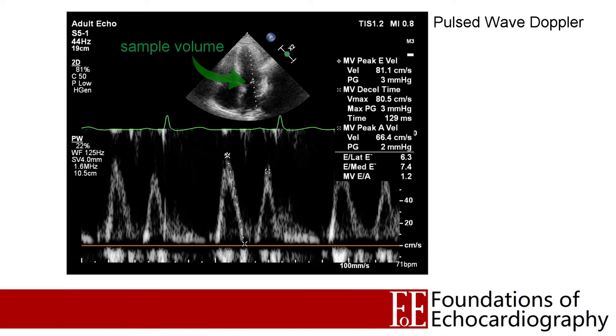Once the ultrasound machine has deduced the velocity of the moving blood and the direction that blood is travelling — either towards or away from the probe, based on whether the frequency has shifted to a higher or lower frequency — it needs to display that information in a way we can understand. For a single point in space it can create a graph where time is displayed across the x-axis and blood velocity along the y-axis, which by convention displays blood moving towards the probe as above the baseline and blood moving away as below the baseline. This is referred to as spectral Doppler.